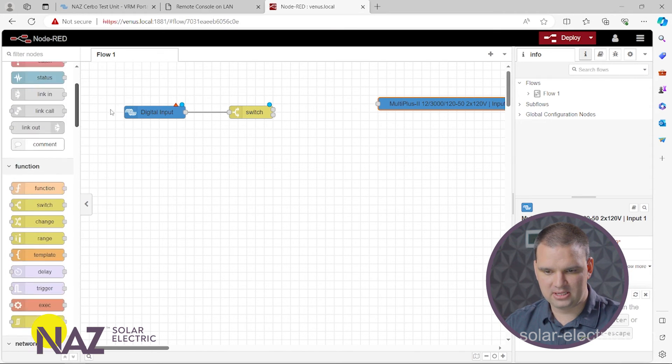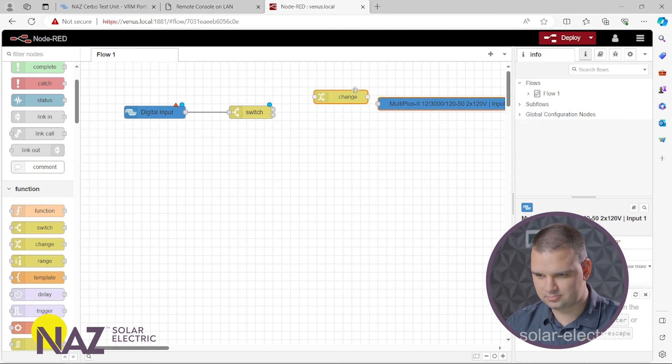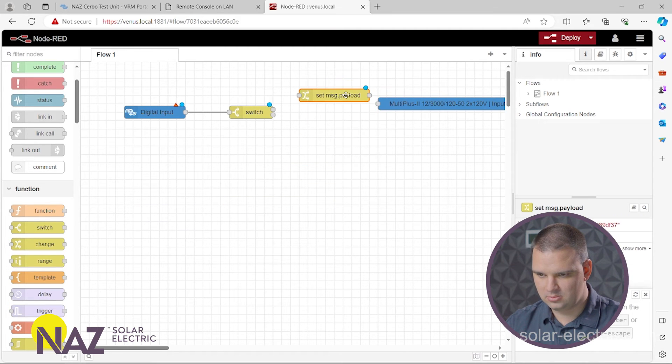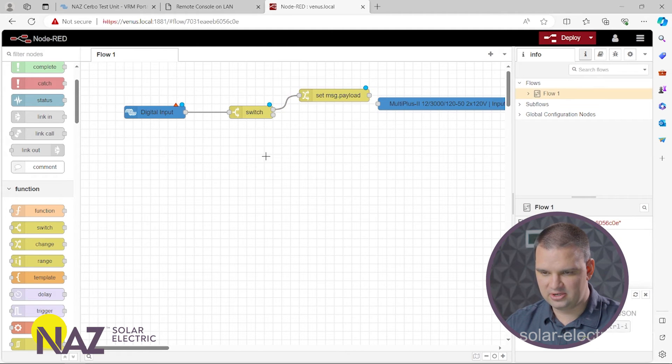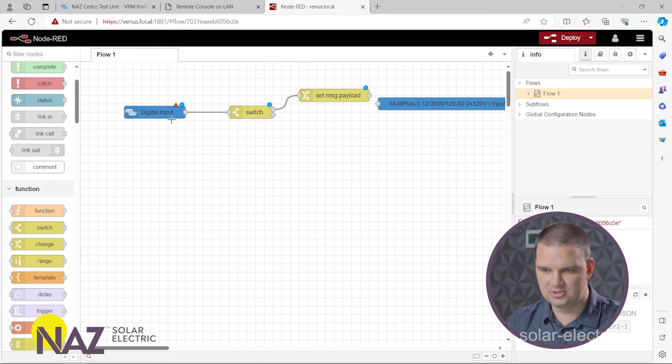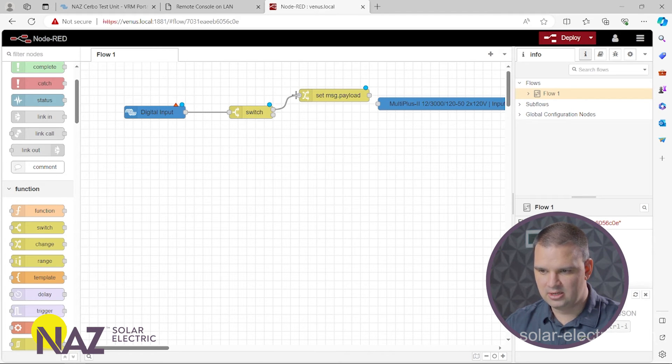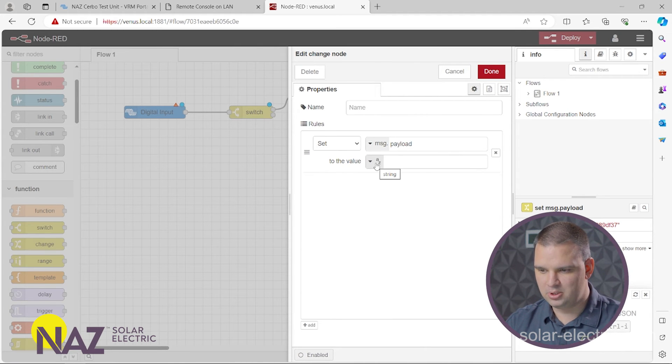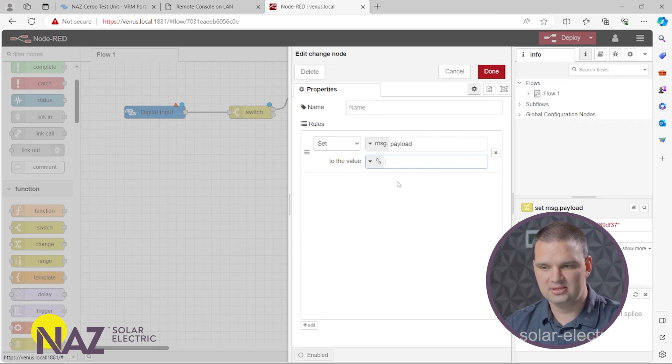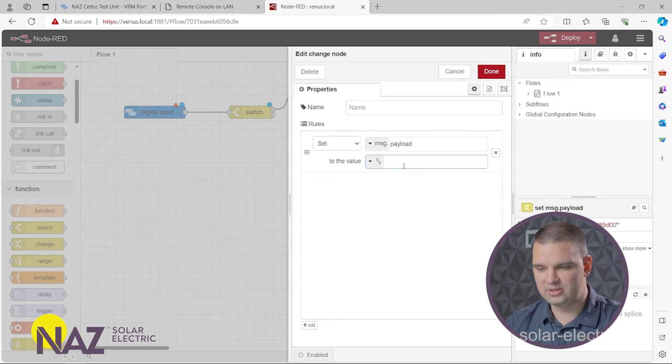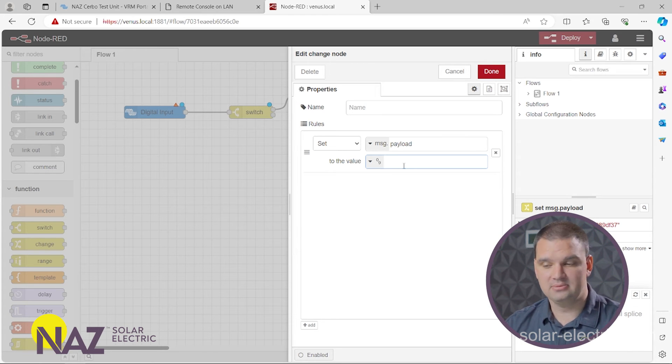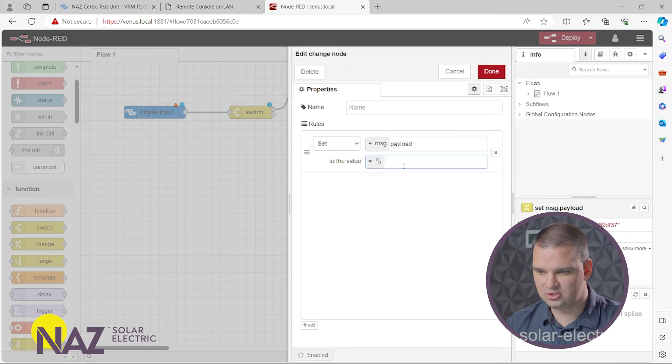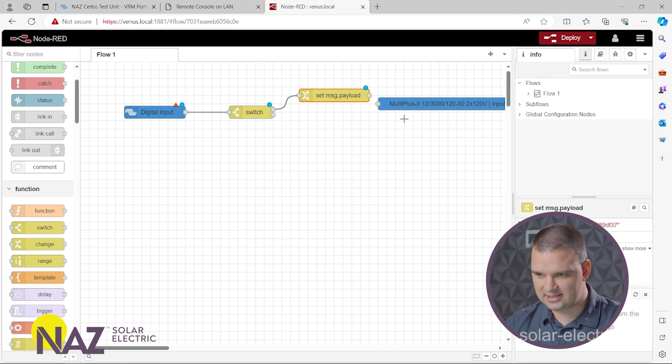And now we need to tell the inverters how many amps to push. So we'll do that by using the change node. So the generator is running. We're going to have a 10 come to the switch. And then that's going to come up to here. We're going to want to set the payload to a number. And this is how many amps that your generator can provide the inverter without overloading. For this application, the generator we have is limited to 22 amps. So we're going to do 22 amps. And then we're going to connect that to the inverter one right here.